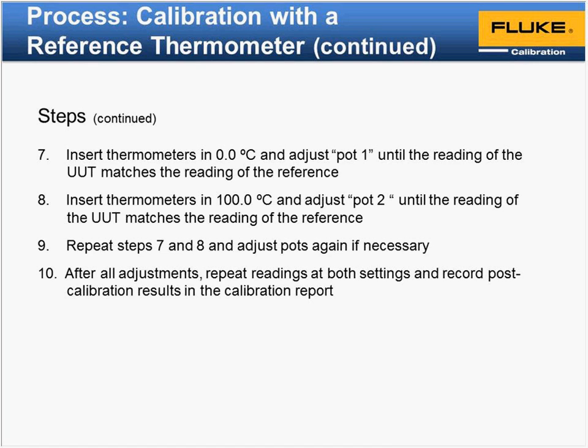A lot of times folks will do just a quick check. Every time you make an adjustment, you should validate that adjustment. Don't just go back to zero and say, okay, I've tweaked it at zero, and I know 100 was good last time I looked at it. Anytime you make a change, you have to go back through and revalidate across the range that you're working.